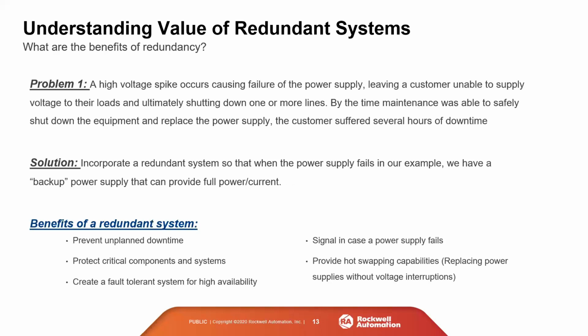So problem 1, a high voltage spike occurs, causing failure of a power supply, leaving the customer unable to supply voltage to their loads and shutting down 1 or more lines. So the solution here would be to incorporate a redundant system so that when the power supply fails, we have a backup that can supply the full power or the current. The benefits of this, obviously, are that we prevent unplanned downtime, protect critical components, and create a fault-tolerant system. There's a signal in case of a power supply failure, so you can have a fail-safe. And there's a new feature on some of our power supplies that we'll talk about later that allows them to be hot swapped, which is pretty cool. So we can go in without any interruption.